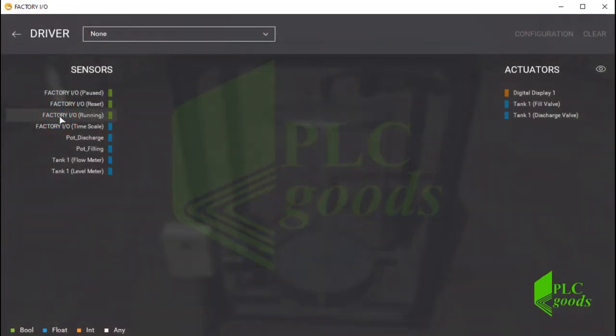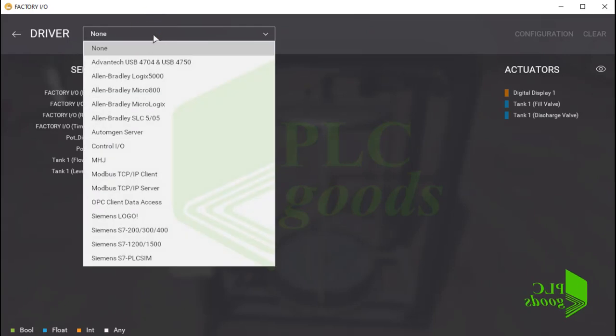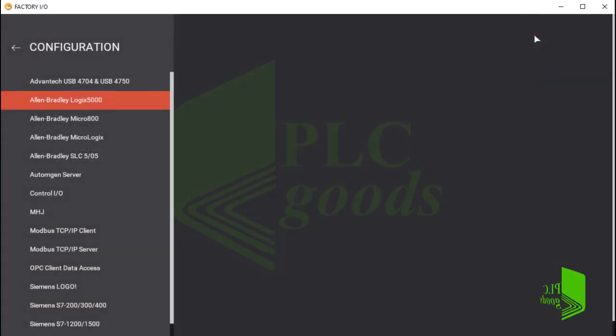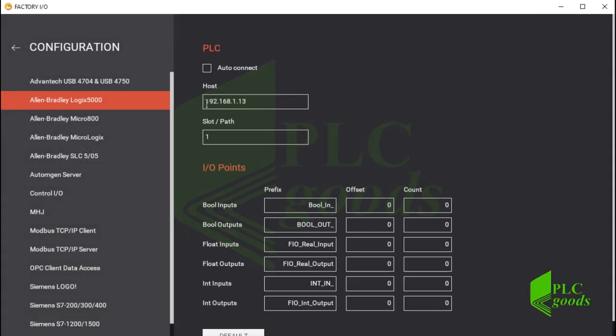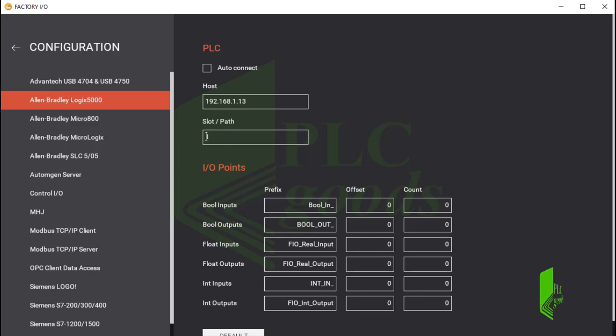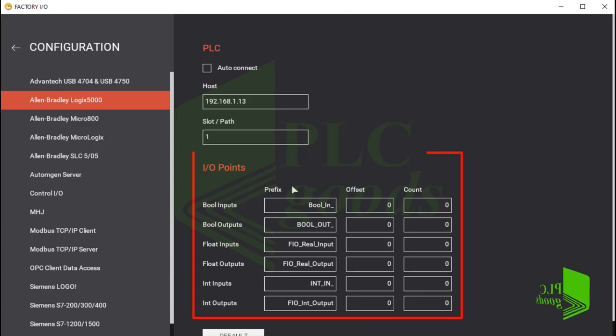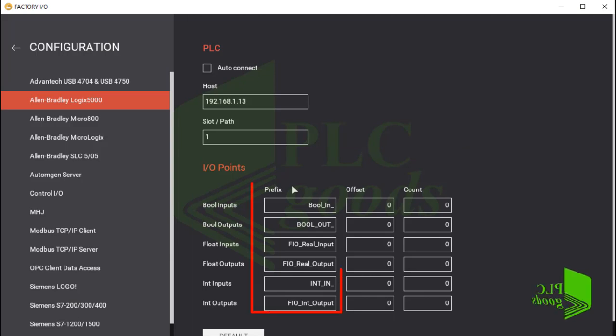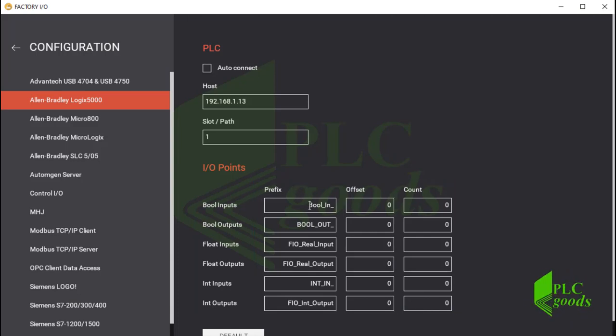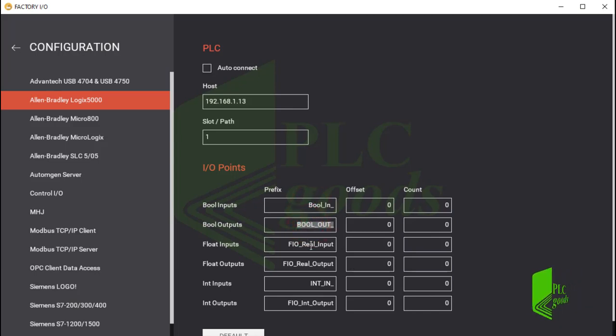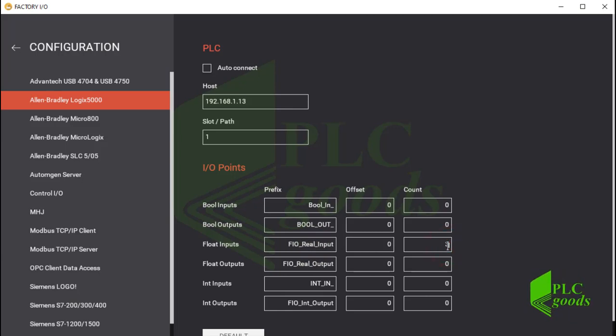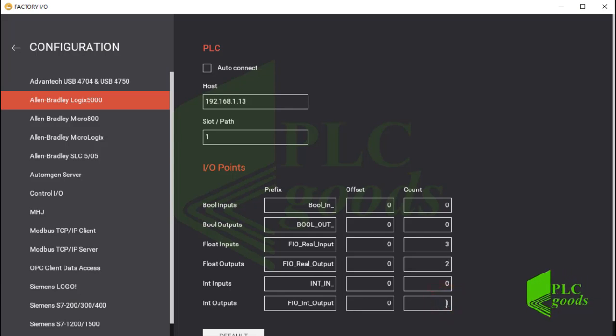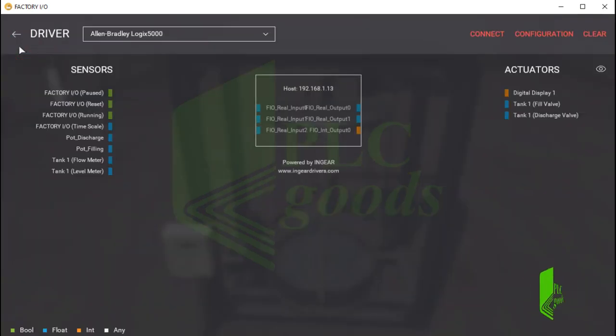Let me click on drivers to do the necessary settings to connect the inserted tank and other equipment to my controller. First the controller type must be selected. Then in the configuration window I must select my controller IP address and also its slot number. Then some suitable tags must be defined here. The inserted equipment will connect to these tags later. These tags will be defined and used inside RSLogix 5000 software. I prefer to not change these tags, but I need to modify the count column.